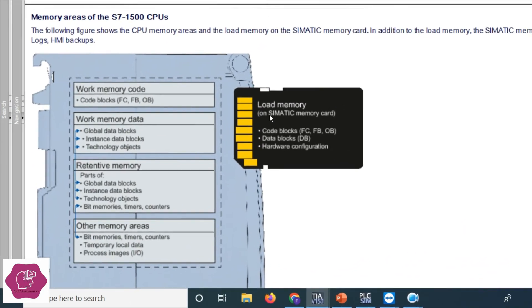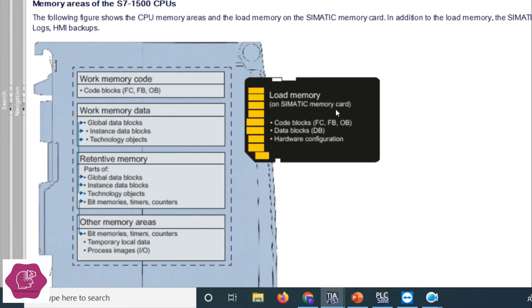Load memory is on the SIMATIC memory card. When the CPU first starts from stop, it loads the data in the load memory area. The type of data stored includes: function blocks (FB), function calls (FC), organization blocks (OB), data blocks (DB), and hardware configuration. That data is stored in the SIMATIC memory card as load memory.